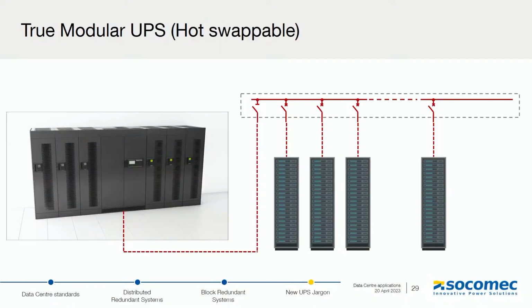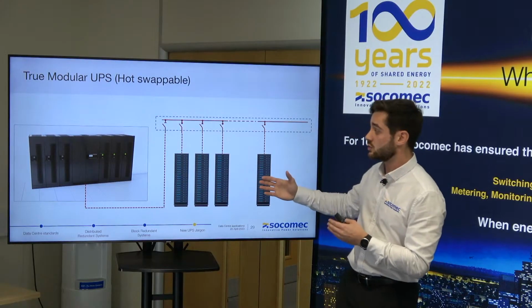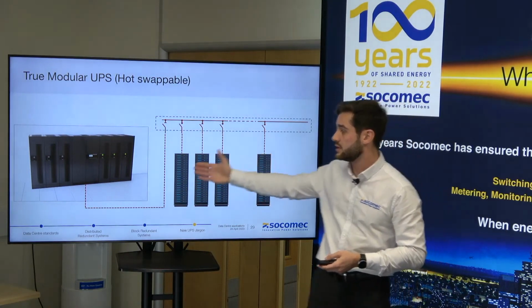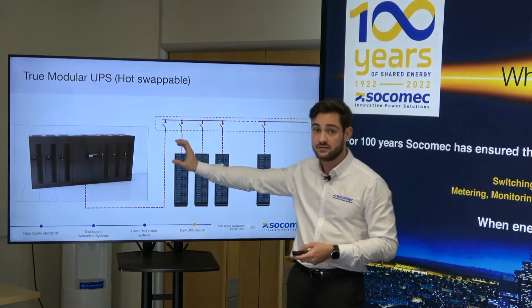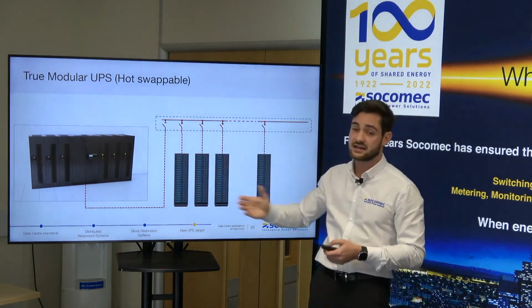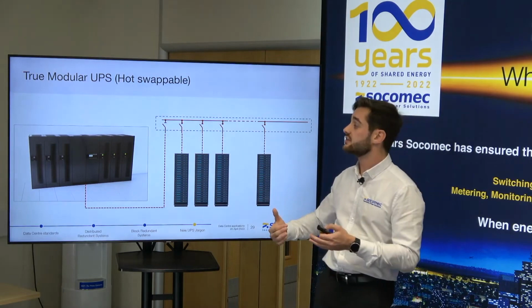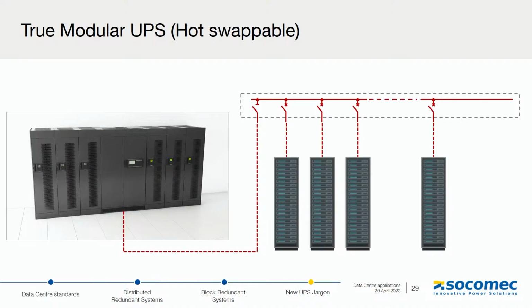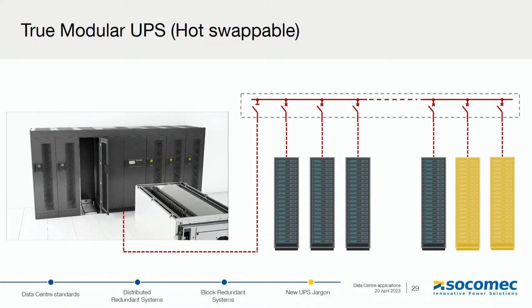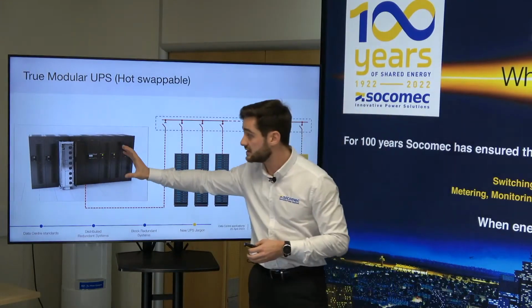On a modular UPS system, we can mention a true modular UPS system when we are able to certify hot swappability. What we mean by hot swappability is, imagine day one you've got, for example, 3 or 4 UPS modules fitted inside, each rated in that case at 200 kilowatts. And then later on you want to increase your load, so you need to increase the UPS power installed as well. You can actually do that online in double conversion, and it's hot swappable because you don't need to switch onto the bypass of the UPS system. In that case, you just need to open the door, fit a new module, make the right connection, and while you're doing this, everything is live.